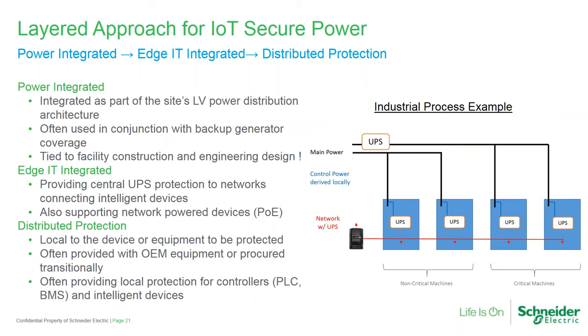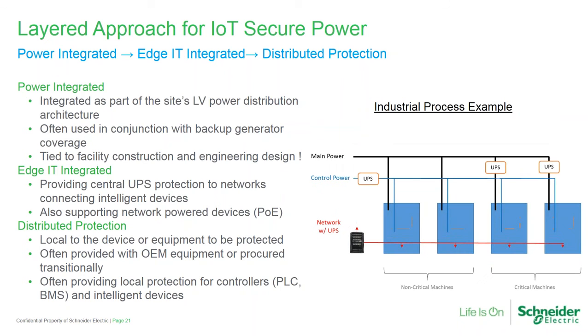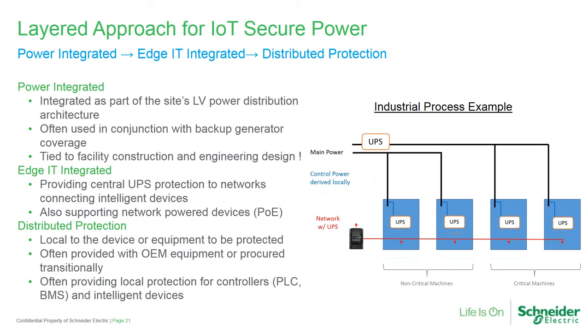I wanted to show an alternative example of how you could do this—there are variations in between. You could apply this to a building management system too, but using an industrial process example. Here I show a couple of UPSs on critical machines and a central UPS for control power. An alternative approach would be a single centralized UPS backing up a number of critical machines, with control power derived locally at the machines via a local UPS.